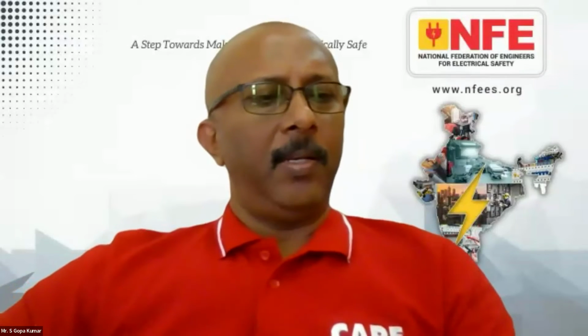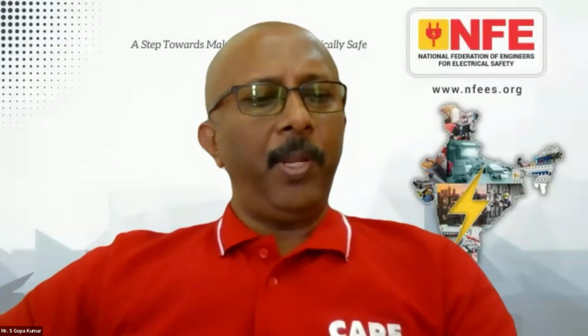Thank you, Mr. Hari. Ravichandran sir, now the question to you. What is your opinion on active harmonic filters? The active harmonic filter is an evolved technology, but in my opinion, I have a difference of opinion with Professor Chilikuri, because IEEE 519 is based on PCC. Depending on the short circuit current level, they are allowing harmonic distortion up to a certain extent. No need of any control. And another thing, either active or passive, if it is oversized only by looking at the TDD, it is going to increase the impedance and there will be a negative effect that worsens the system. So it has to be appropriately sized.